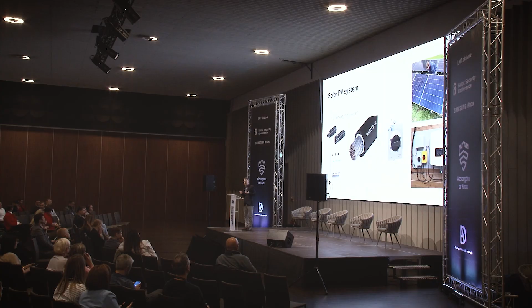What can we do to prevent those issues? Generally, where we can, we try to use factory-made patch cables, regular inspection and testing, arc fault detection systems, and we could consider use of optimizers and microinverters. Those devices will limit the DC voltages on the system, and that would reduce the risks and dangers of the DC arc magnitude.